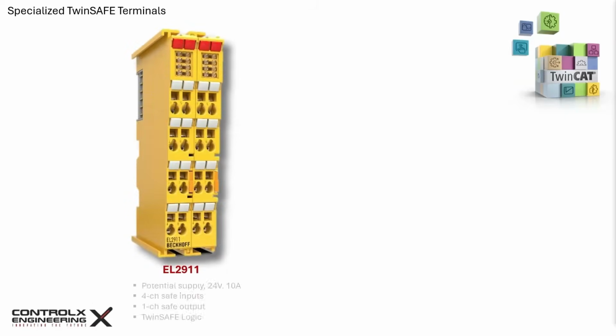Next, I want to highlight a few special TwinSAFE modules which combine logic and I/O on the same terminal. The EL2911 is a safe potential feed terminal for the power contacts. In addition, it has 4 fail-safe inputs for sensors with potential free contacts for 24-volt DC and 1 safe output with 10 amp driver. This terminal also features integrated TwinSAFE logic functionality similar to the EL6910. With the help of locally available inputs and outputs, a complete safety application can thus be realized directly on this terminal. It also has a variant, the EL2911-2200, which does not have the logic functionality and is a pure I/O variant only.